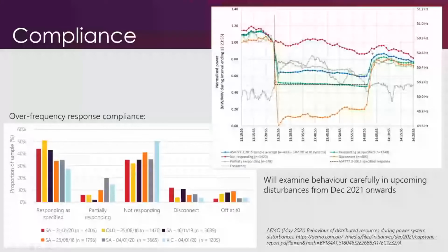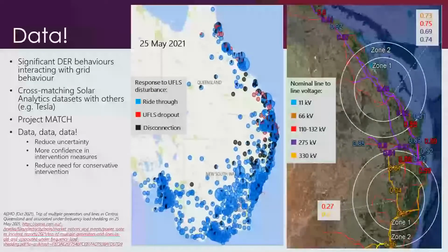Why they were not responding is somewhat unknown, whether they were not set to the correct standard or whatever the reason is. So we are waiting with bated breath to see how inverters respond across not just overfrequency droop, but all of the different parameters in the new 2020 standard, to see how they actually perform in the field. This will be a really critical step to observe, to see that they are actually reducing disconnection rates with that new standard. All of this is underpinned by very, very large data sets that we've had to work with to understand what tens of thousands of inverters are doing, to get a decent sample and understand what the fleet of millions and millions of devices are doing across the NEM.